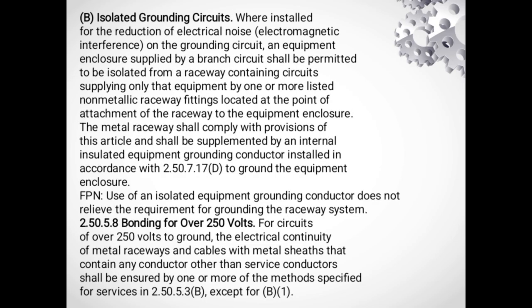B. Isolated grounding circuits. Where installed for the reduction of electrical noise, electromagnetic interference on the grounding circuit, an equipment enclosure supplied by a branch circuit shall be permitted to be isolated from a raceway containing circuits supplying only that equipment by one or more listed non-metallic raceway fitting located at the point of attachment of the raceway to the equipment. The metal raceway shall comply with provision of this article and shall be supplemented by an internal insulated equipment grounding conductor installed in accordance with 2.50.7.17d to ground the equipment enclosure. FPN. Use of an isolated equipment grounding conductor does not relieve the requirements for grounding the raceway system.